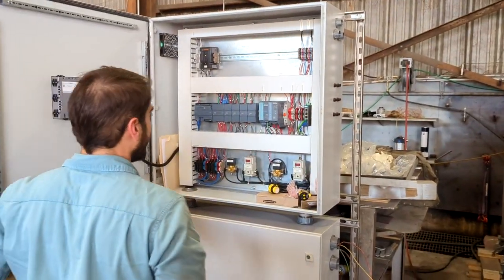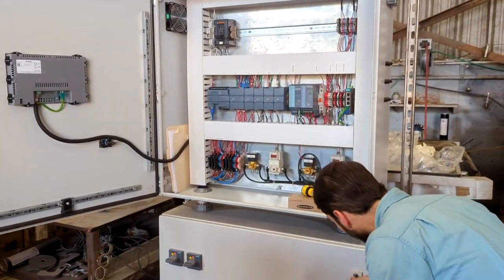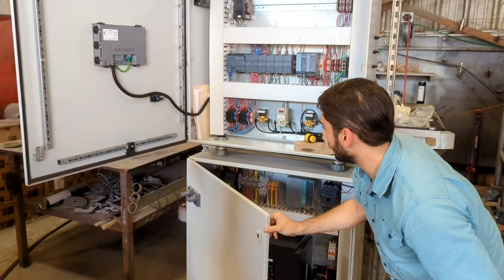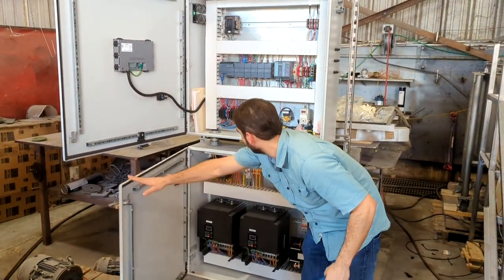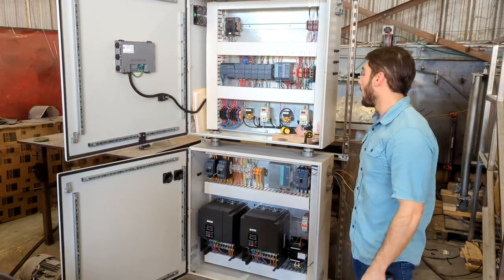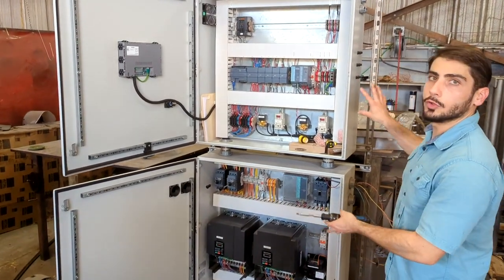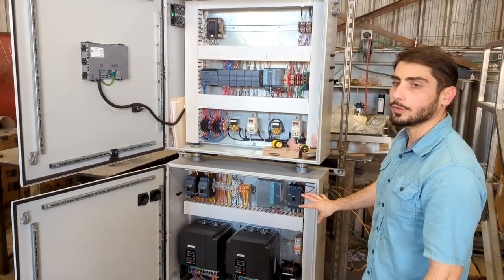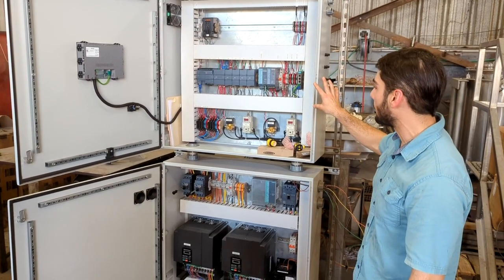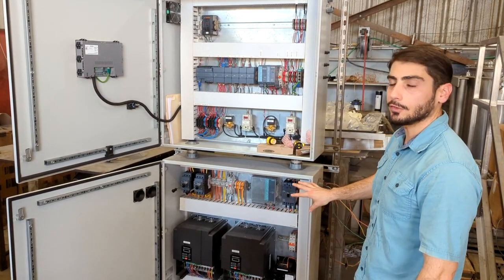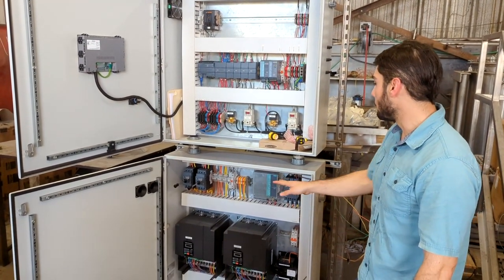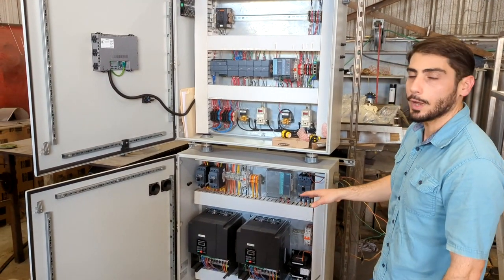You get a good look at the PLC we got in there. That's the brains of the control panel and what's going to be used to control the machinery. How we do our controls is separated into two compartments. We have a high voltage cabinet isolated from a low voltage cabinet. All of the 480 three-phase takes place in here. We have two motors that we're controlling, 230 horsepower.